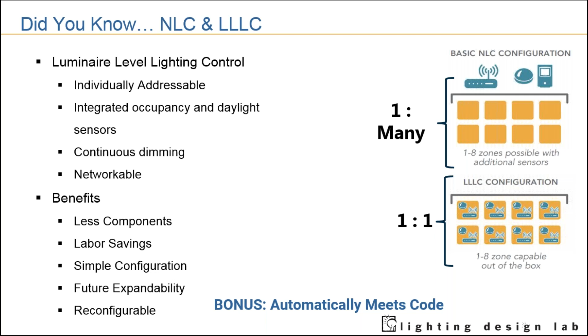A great way to describe this, also part of our best practice guides from last year, is the one-to-many and one-to-one relationships. When not using an LLLC configuration, you're using zone control: one load controller and a set of sensors, maybe a couple of corner-mount sensors or ceiling sensors, for many fixtures. LLLC has a one-to-one relationship—one sensor, one load controller, one fixture.